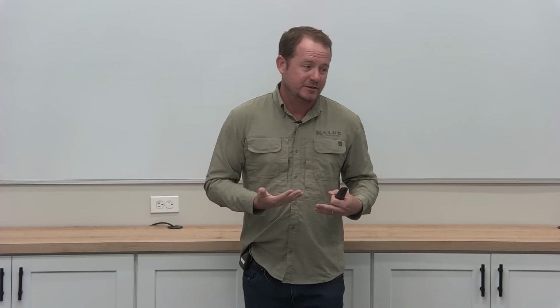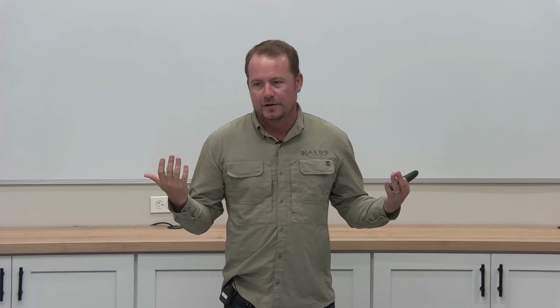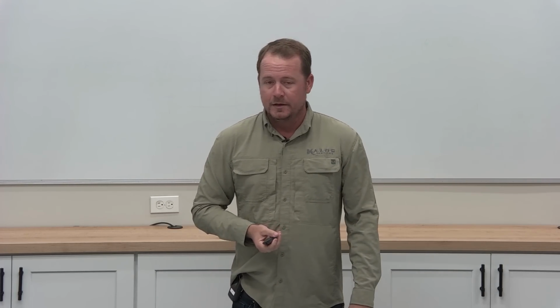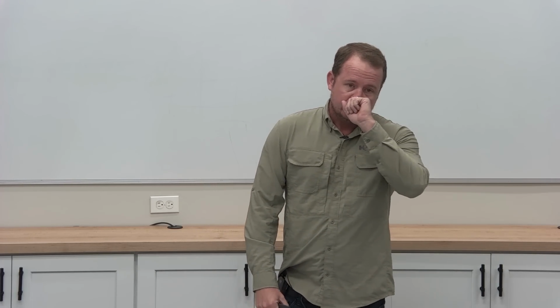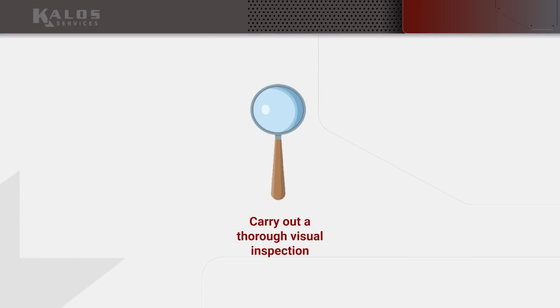I'm specifically mentioning gas pool heaters because that's really the only ones that we see this a lot in Florida. In Florida, our furnaces run so rarely that you're rarely going to run into a situation that you find a rusted out cabinet or a rusted out burner assembly on a regular furnace. But if you did, then that would also be something to pay attention to. What are some other things in a visual inspection?